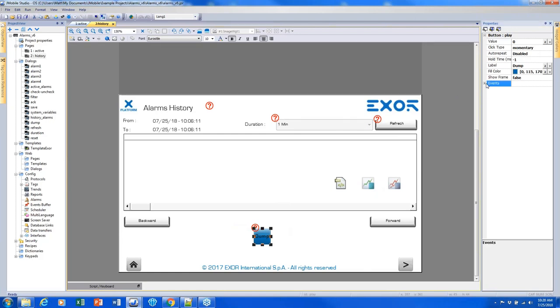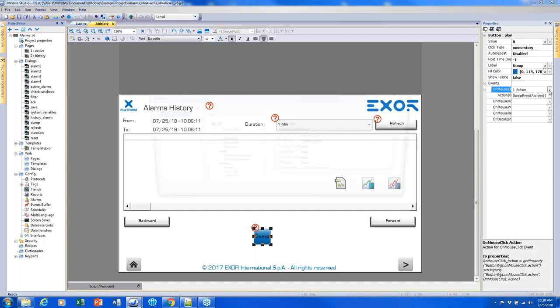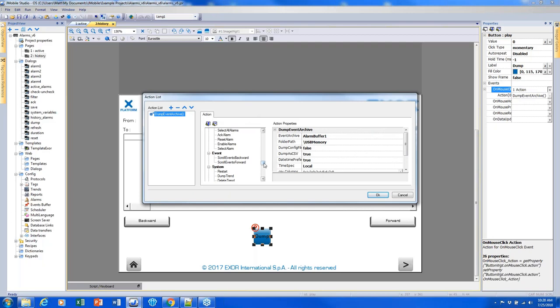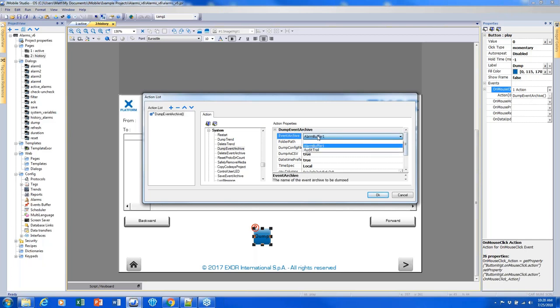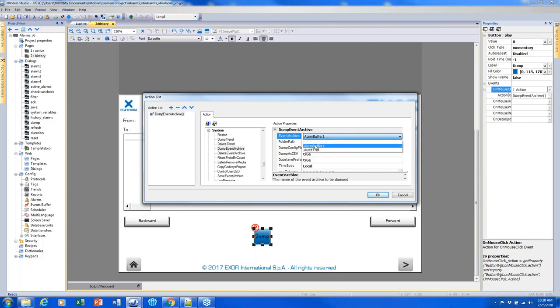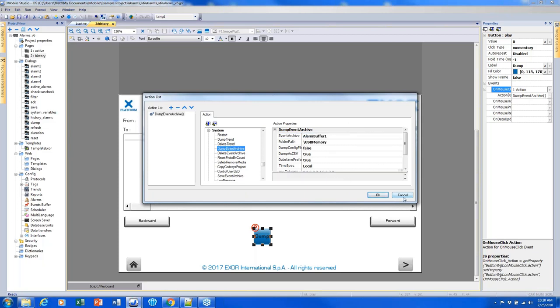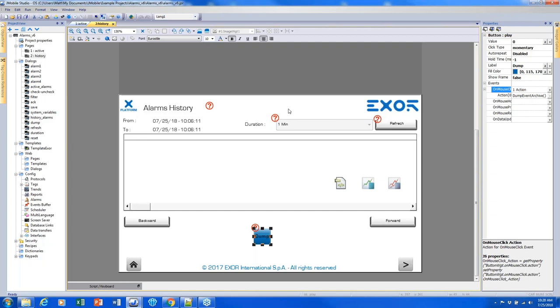The second page is the historical alarms page. During all that time playing with the alarms, you can see a list of the alarms that went off. You can change how long it records — mine is just five minutes. We can refresh this, move forward or backward in time. There's also a dump button. It's possible to record which alarms went on or off during a certain period and save them to a CSV file using the action dump event archive, found under System > Dump Event Archive. You select the folder path and the event archive — in this case, alarm buffer one. On the alarm page, you can create multiple buffers.